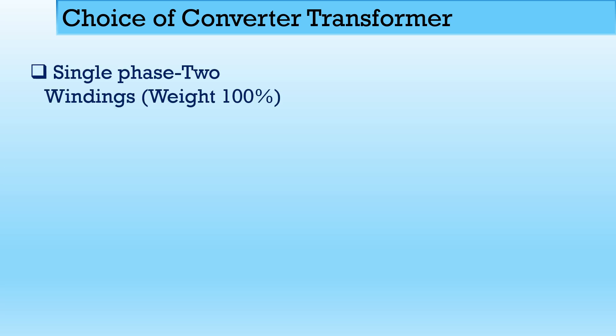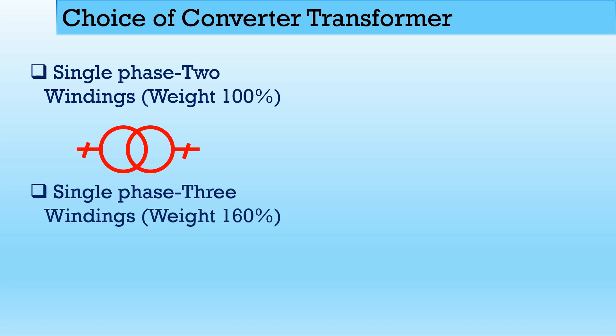There are four choices for the converter transformer. The first is a single-phase two-winding transformer — take its weight as 100% — with one primary and one secondary, supplied by single-phase supply; three units can be connected in star or delta as required. The second is a single-phase three-winding transformer, with one primary winding and two secondary windings, all connected to single phase; three such transformers can be connected to form a star-star, star-star-delta configuration, forming a three-phase unit.